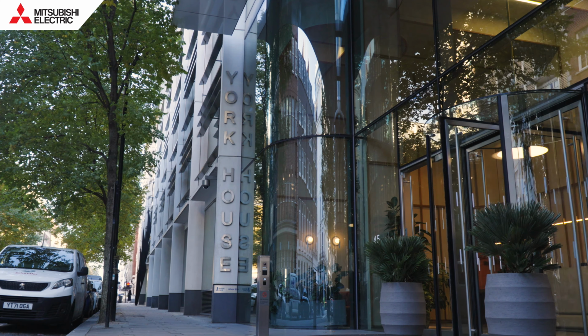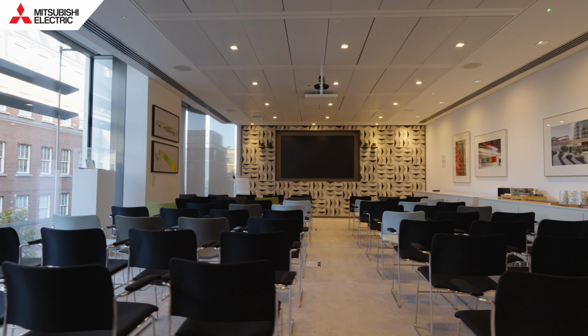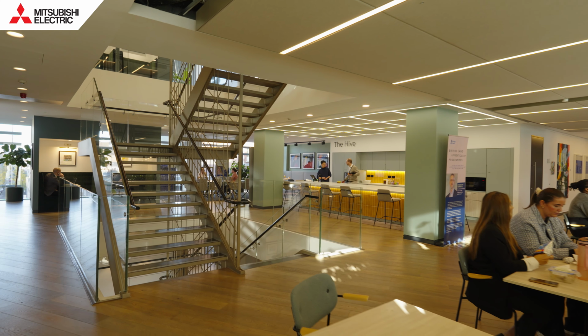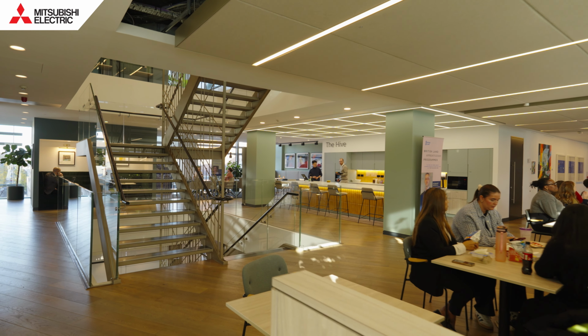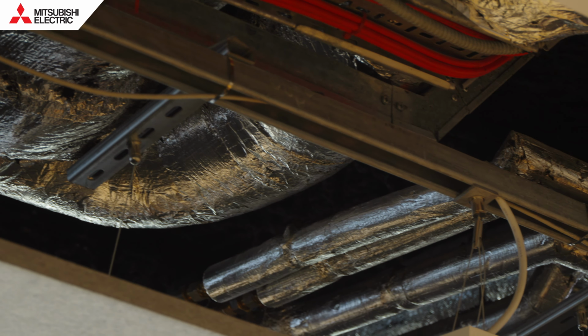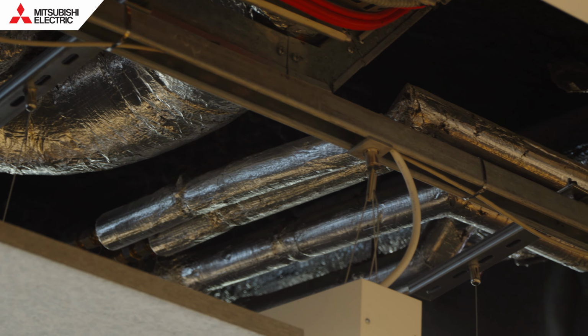What we've managed to prove here is that we can achieve in a building like this over a 400,000 kilowatt hour reduction year on year in energy. And that's not a small feat to achieve as a retrofit. That's one of the key successes that we've been able to do here, to prove that not only have we reduced our carbon and our kilowatts, but also reduced complaints into the building. The British Land sustainability targets are for a 75% reduction in operational carbon and a 25% reduction in operational energy. And these targets are set to be achieved by 2030.